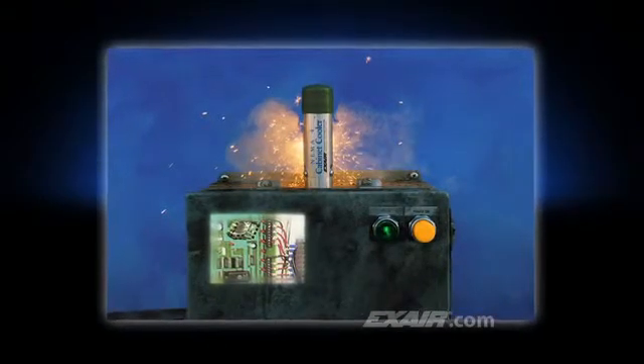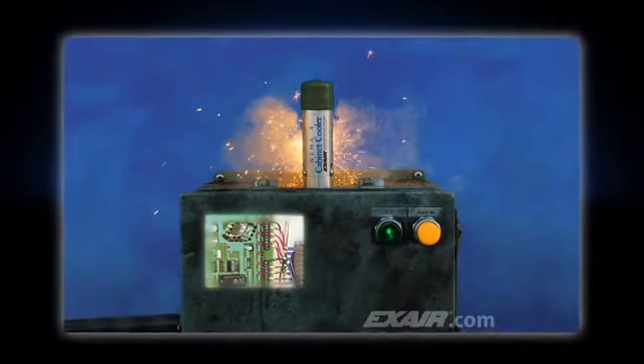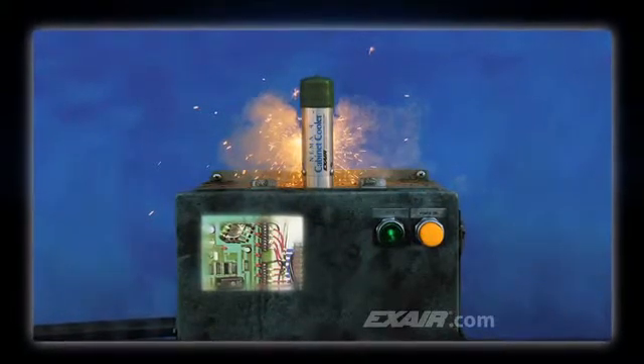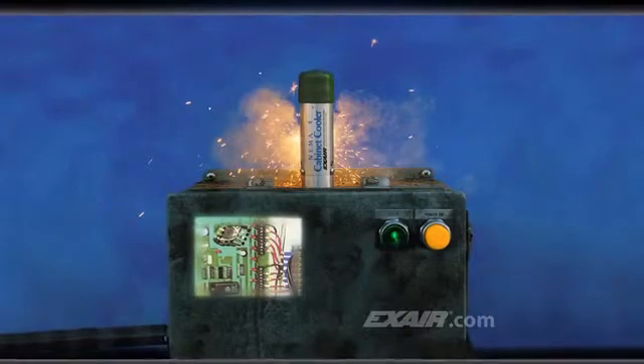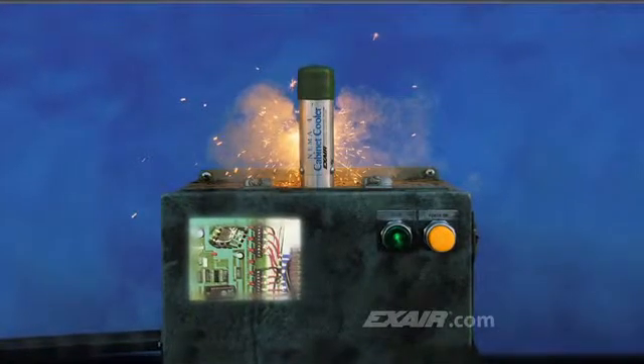They pass 1 SCFM or 28 SLPM of air through the cooler when the solenoid valve is in the closed position. When the thermostat detects high temperature, it energizes the solenoid valve to pass full line pressure to the cabinet cooler, giving it its full cooling capability.